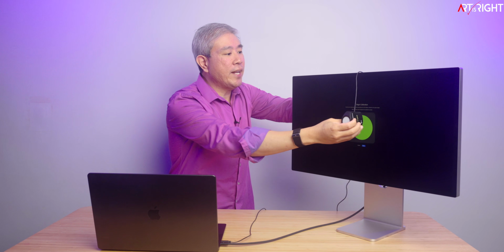So what I'm going to do is hang this on the display and adjust the counterweight to where it is. It's laying flat on the display right now, but for the best result, what you want to do is just lean the display back like so. And simply enough, from this point, you're going to click on begin. Now, this is going to put your display into a full calibration mode. So it's going to take the display out from the system, go through a full calibration.